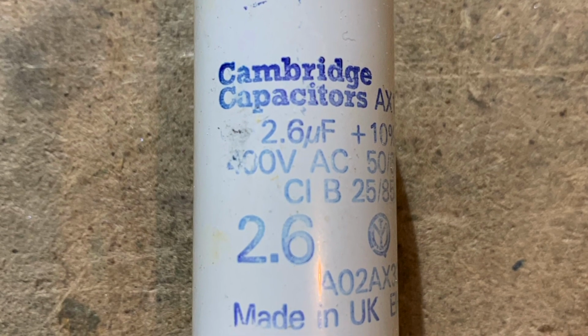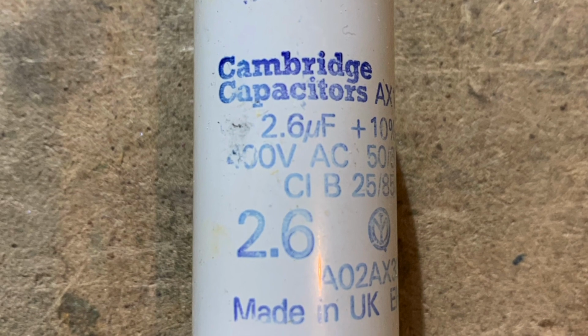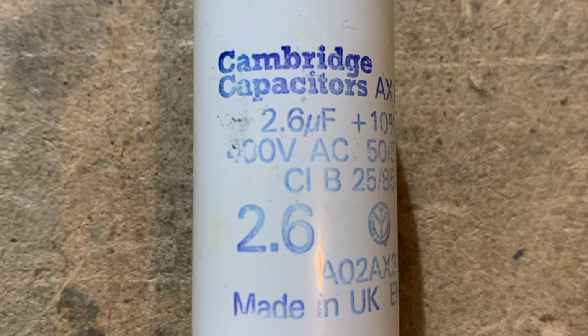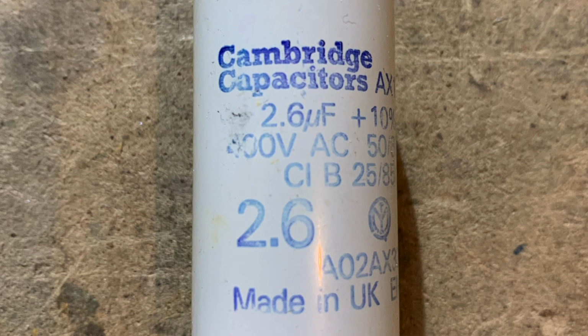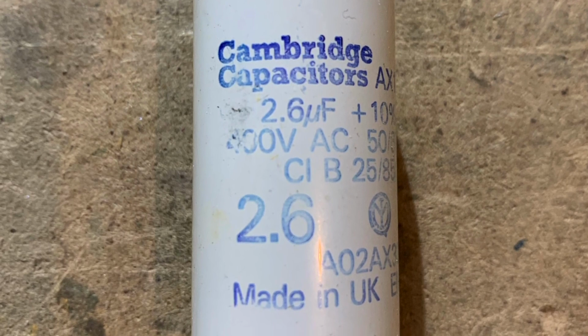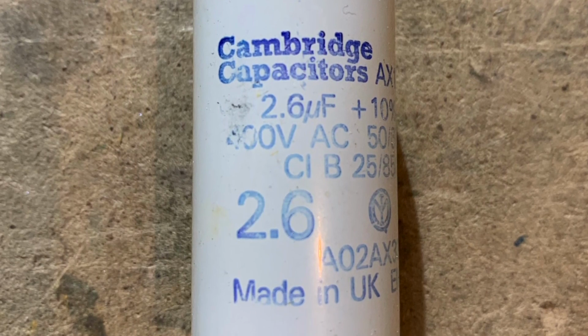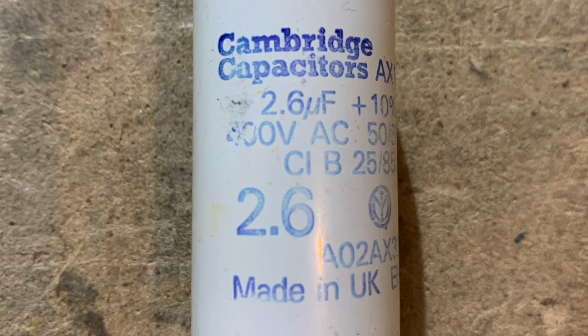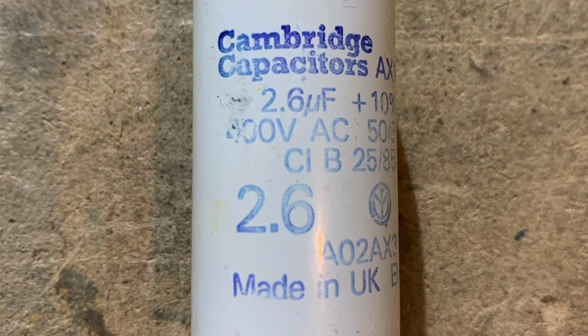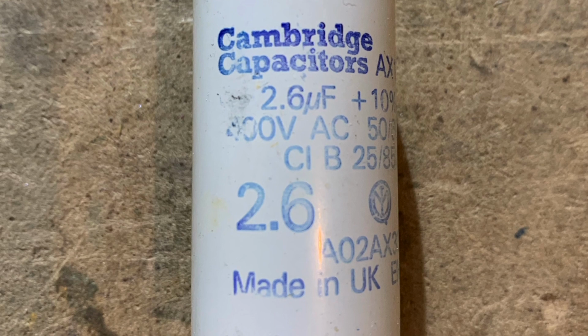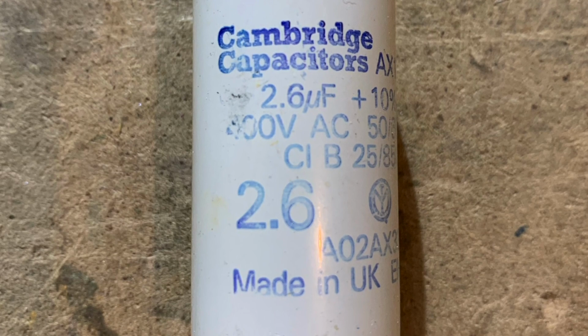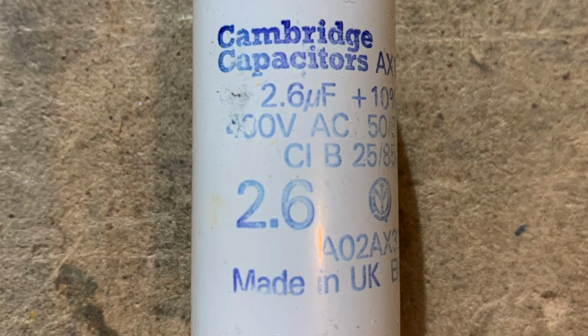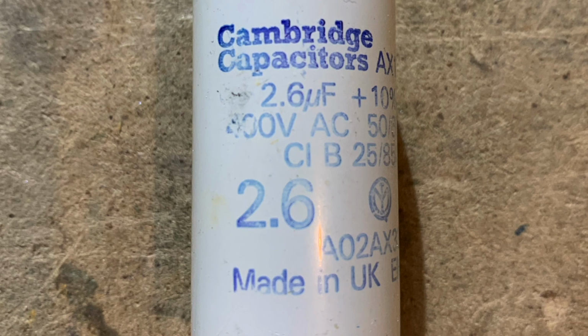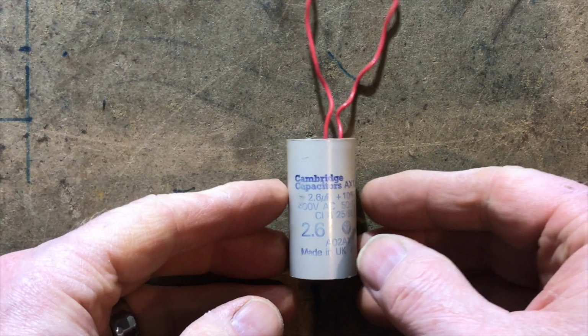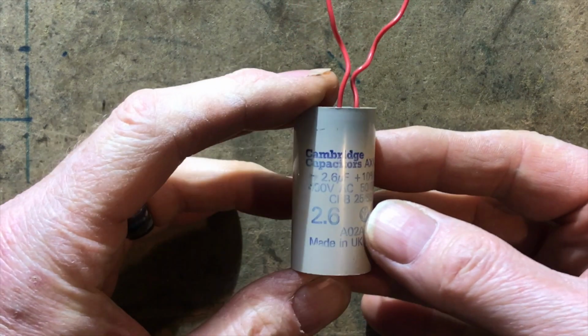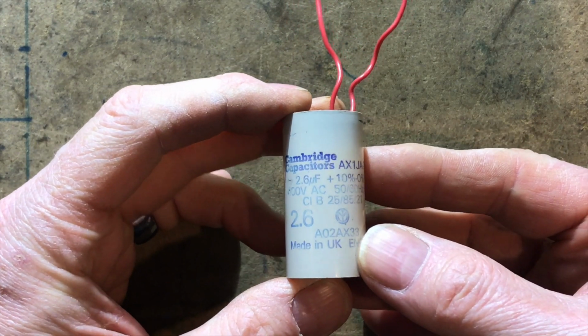Now basically, not going into too much detail, there are two plates in here, and one side stores the energy and the other one releases the energy, and it can draw the energy back from the mains. They are cooled by an oil inside there, so if you did get this brown oil leaking out of them, then they need to be discarded because they're broken. So like I say, this is a start capacitor, and this is what's going to give the pump the energy to be able to move the water on startup, and that's all it does.